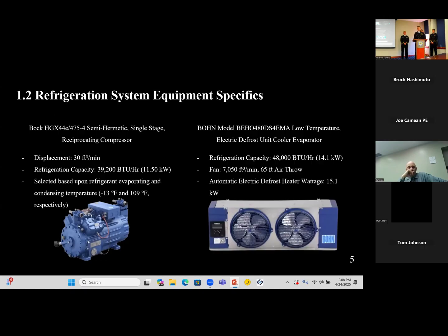Next up, we selected our evaporator, which is a low temperature evaporator with an electric defrost heater unit. This has a refrigeration capacity of 48,000 BTUs per hour, a fan's volumetric flow rate of 7,050 cubic feet per minute, and an automatic electric defrost heater with a power draw rate of 15.1 kilowatts.